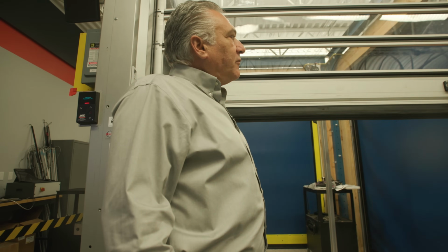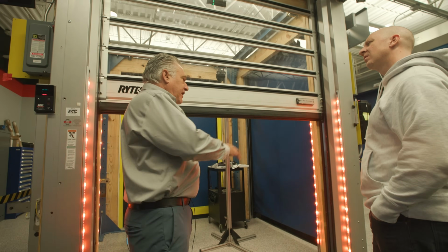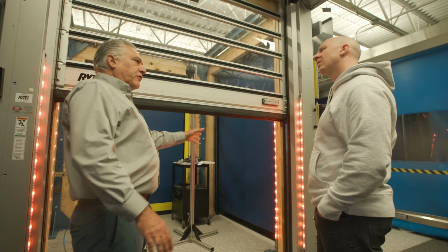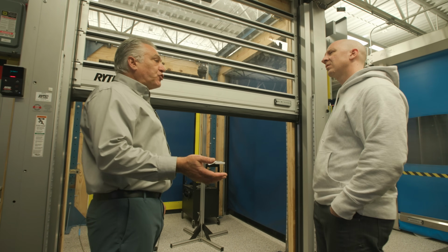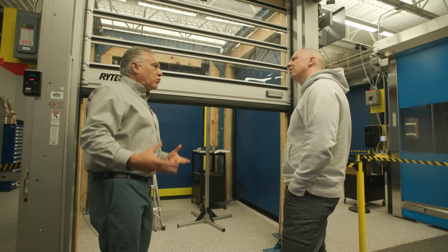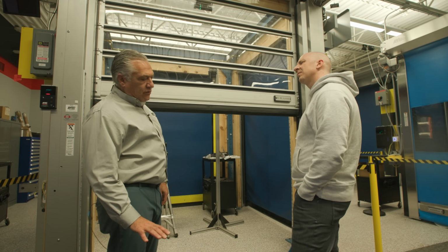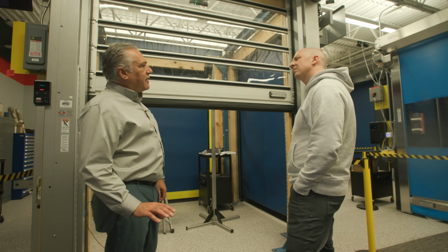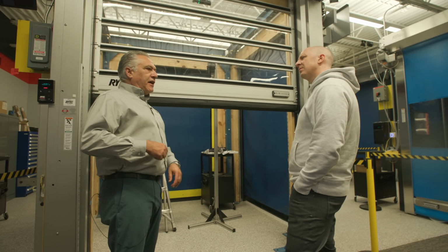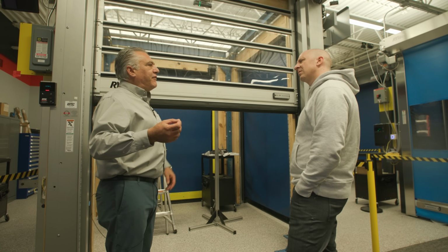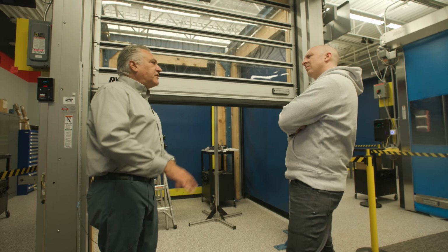So now it's a redundant system? No, it's an option for applications that can't have all the new smart surround system in the door light curtain. So for instance, if you were in a maintenance garage, like an actual working garage, in some cases the garages have a restriction where you can't have any electronics or electrical equipment below 18 inches because of the settling of gas fumes. And in those cases, you would either need to have explosion-proof devices, or you'd have to have no devices below 18 inches.